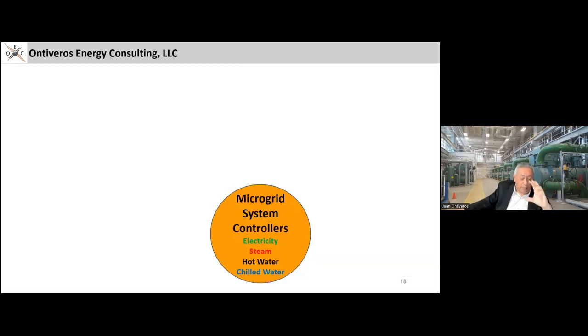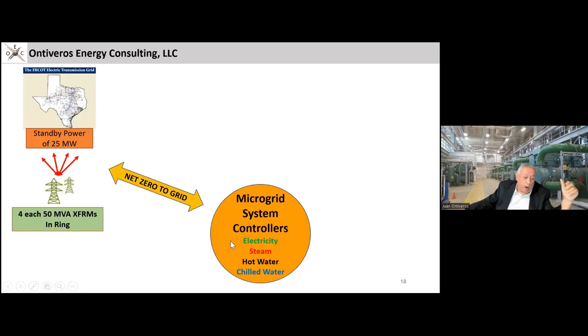So the key to everything working is, yes, you have all the controls and you're balancing all these things, but it's the microgrid system controllers that regulate electricity, steam, hot water, and chill water to your campus. So here we're operating net zero to the grid. We didn't buy any power. We didn't want to buy power or sell power. We always want to be just zero. It was a maximum take of 500 kW.